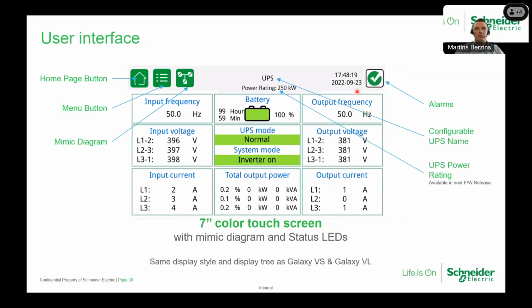So, a 7-inch color touchscreen display where you can see the power rating which the UPS has at the moment, or you have configured. You will see the battery status, the percentage of the battery level, some input-output parameters of frequency and voltage, and of course in which operation mode the UPS is currently working. Is it normal mode or some other inverter mode? And also the total output power. For this particular reason, there is no load attached, so there is no power rating shown here, but this will be displayed once you connect the power.